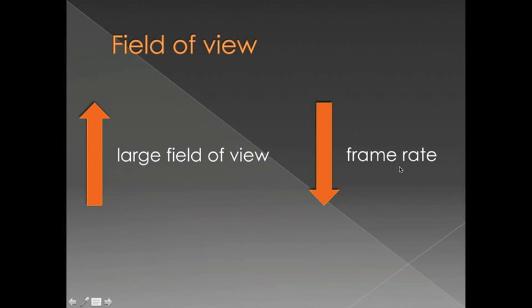Conversely, if you have a much smaller field of view and less depth, it's going to take you less time to get those echoes back to the transducer, and therefore you can draw images much faster, and you'll have a higher frame rate.